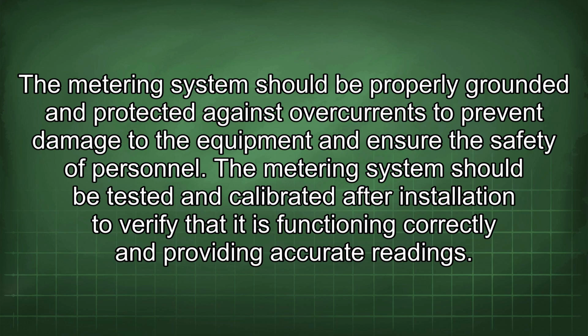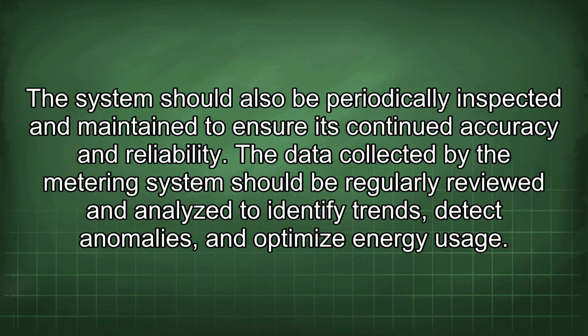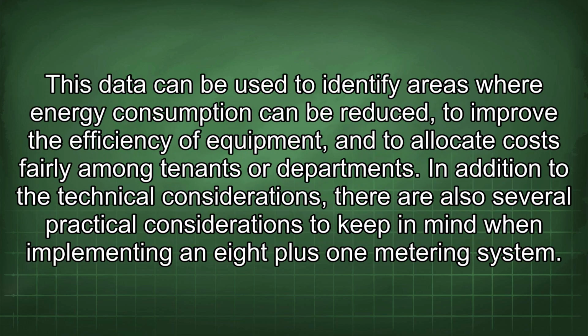The metering system should be tested and calibrated after installation to verify that it is functioning correctly and providing accurate readings. The system should also be periodically inspected and maintained to ensure its continued accuracy and reliability. The data collected by the metering system should be regularly reviewed and analyzed to identify trends, detect anomalies, and optimize energy usage. This data can be used to identify areas where energy consumption can be reduced to improve the efficiency of equipment and to allocate costs fairly among tenants or departments.